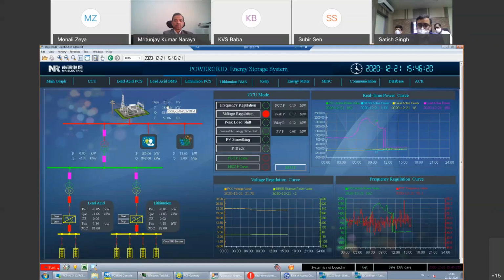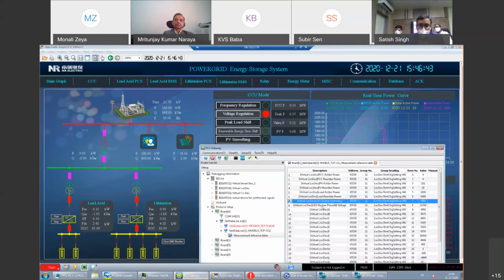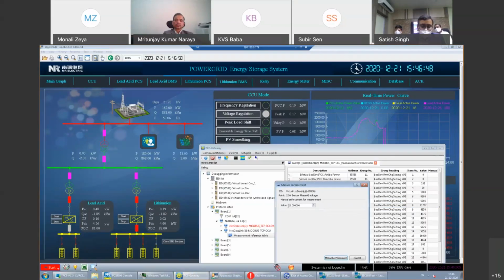Now for the voltage regulation module, the dead band we have decided is 20.9 to 23.1 kV with respect to 22 kV. So this 21.7 is within the range, and hence the reactive power output from the battery is now almost zero. Now you enable. The problem here is we cannot wait for the voltage to change so that we see the Q output response, because this is an open loop system, where input affects the output, and output has no role to play with the input. So we will change the input values manually for a few of the parameters, and let us see how the battery is responding.